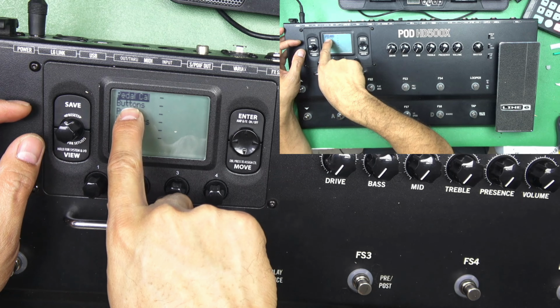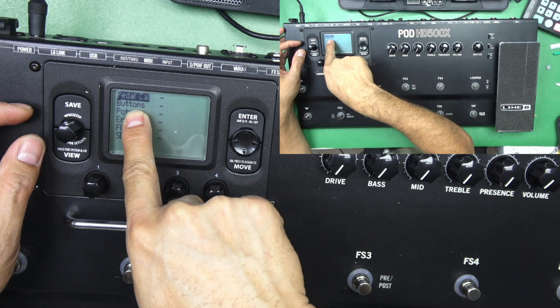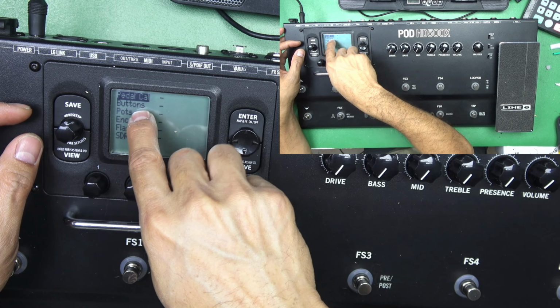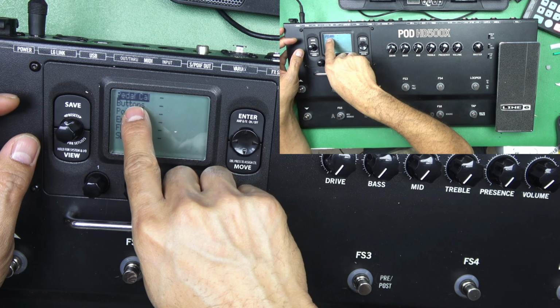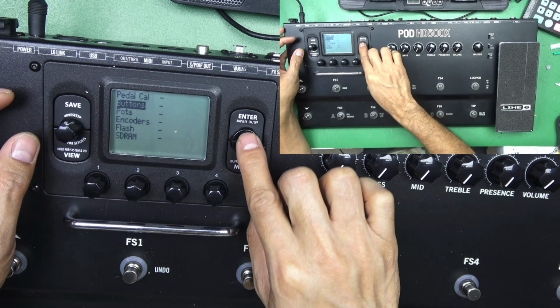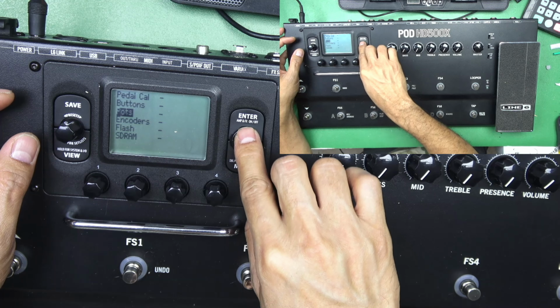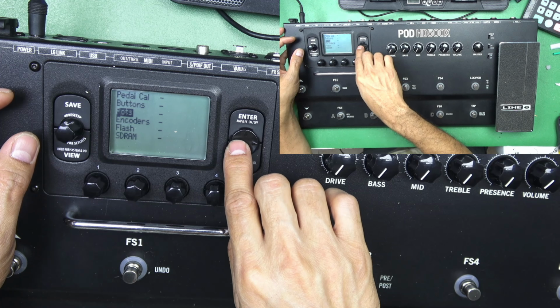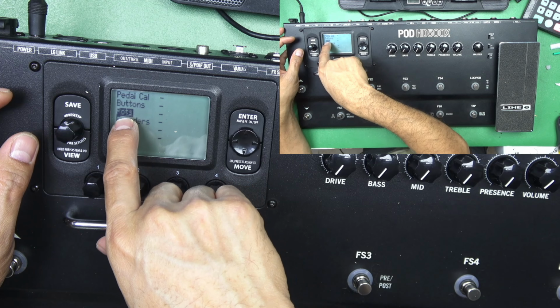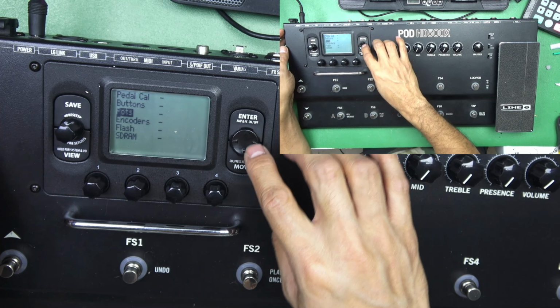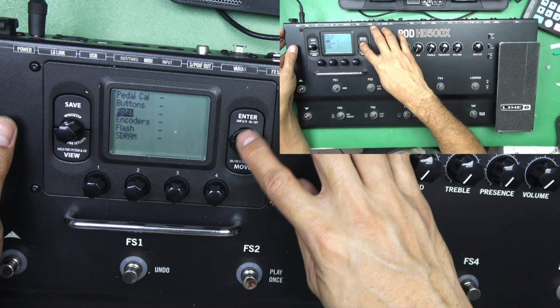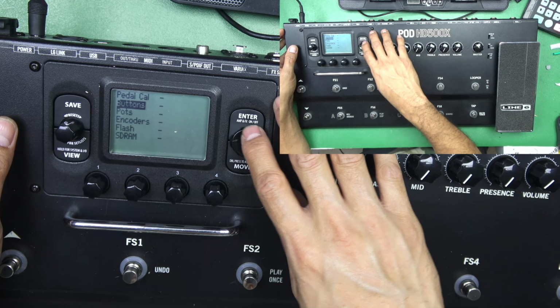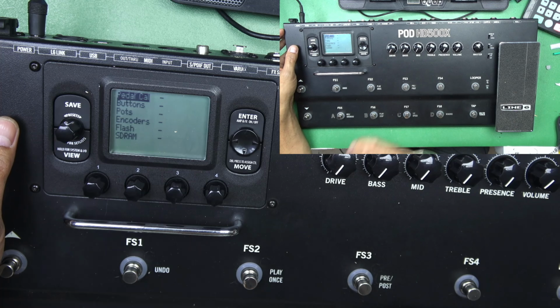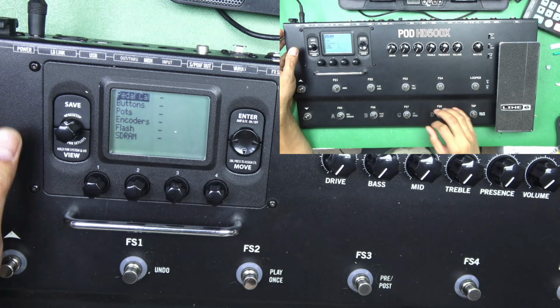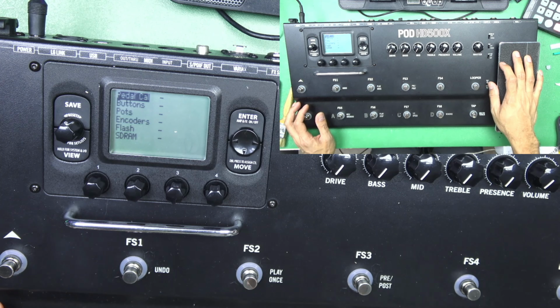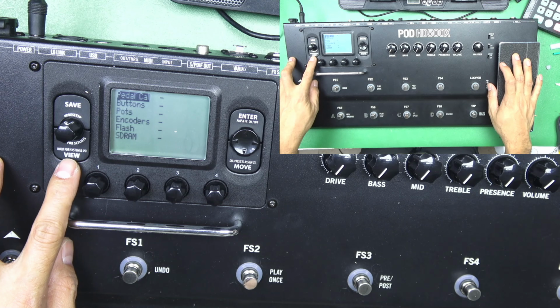As you can see, in our view, the highlight is on pedal calibration. If you found that the highlight is not on the pedal calibration, you have to use the arrow up and arrow down to select.